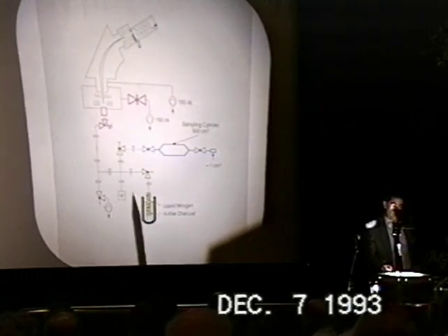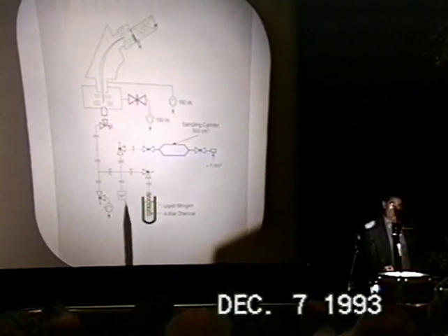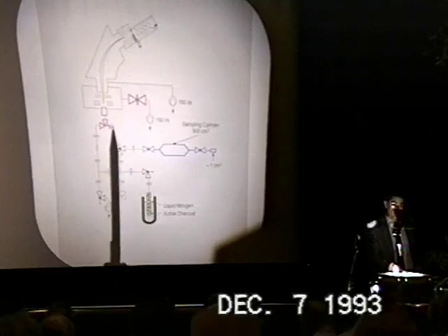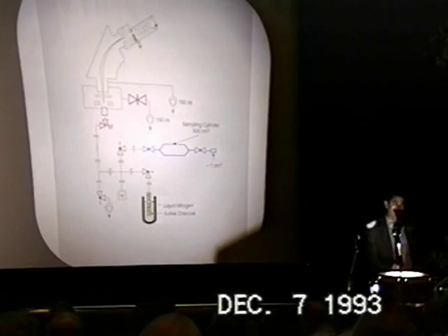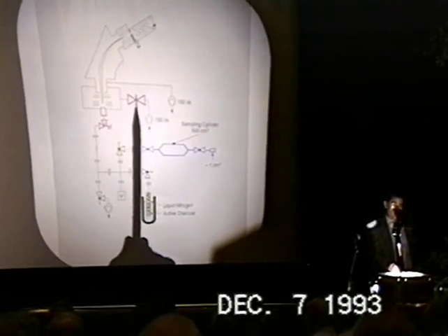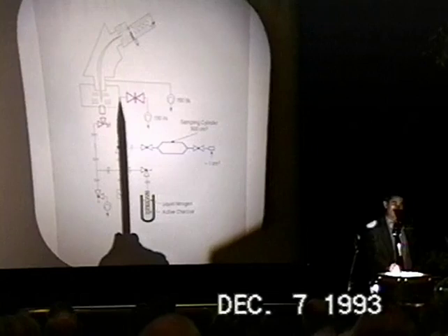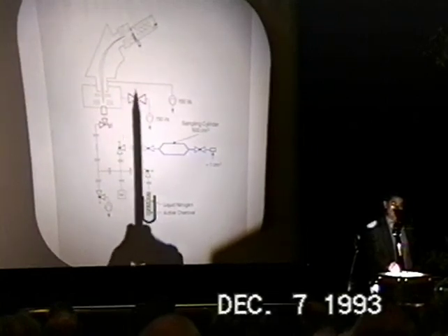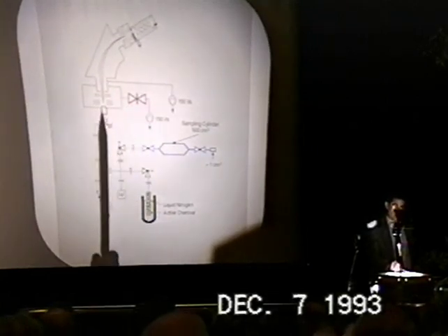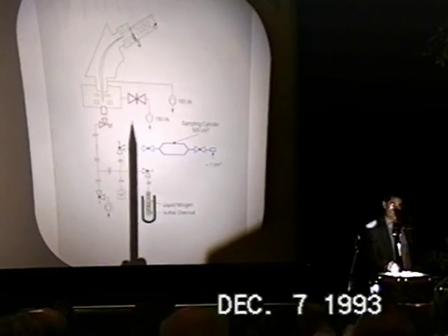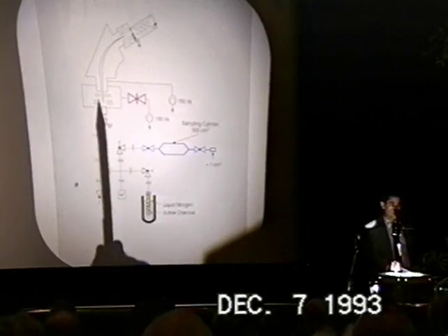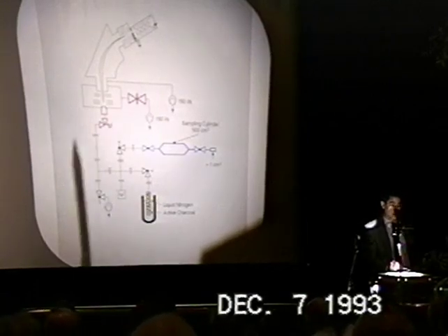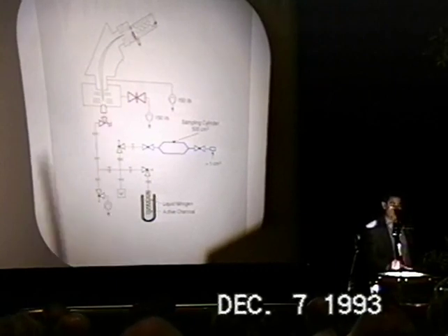Actually, by allowing it to expand, the pressure goes down to 10 to the minus 2 torr approximately. At that stage, before admitting the sample into the ion source, we shut off the pumping into the ion source only. By taking advantage of the differential pumping of the mass spectrometer, the partial pressure of helium inside the ion source goes up and subsequently falls down.